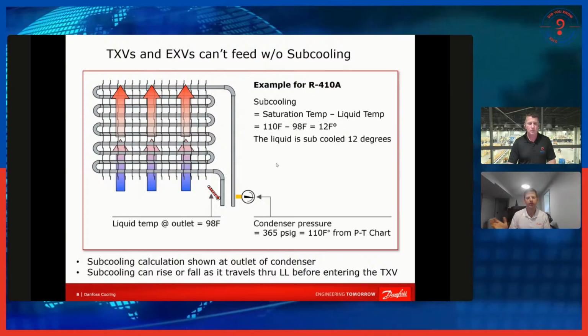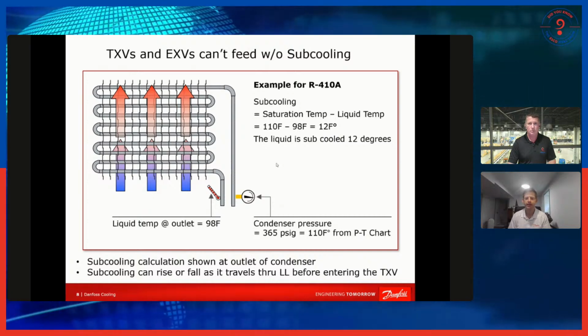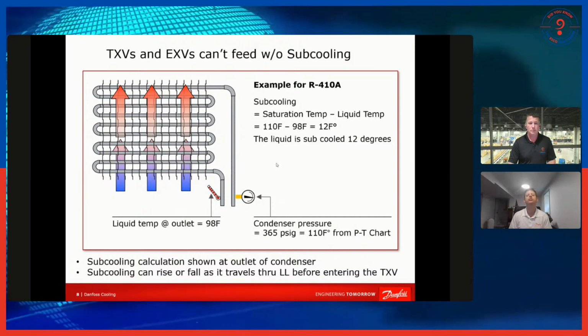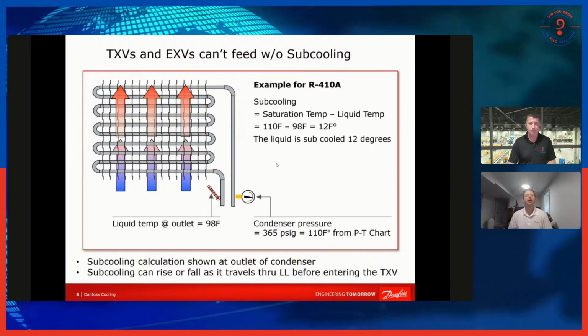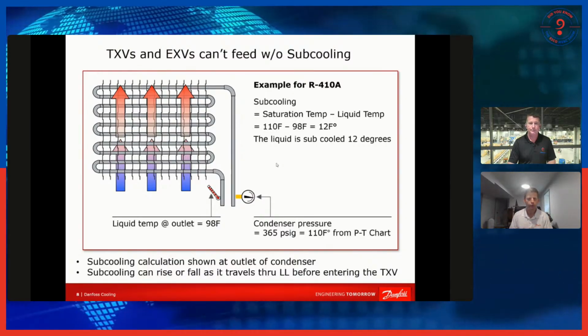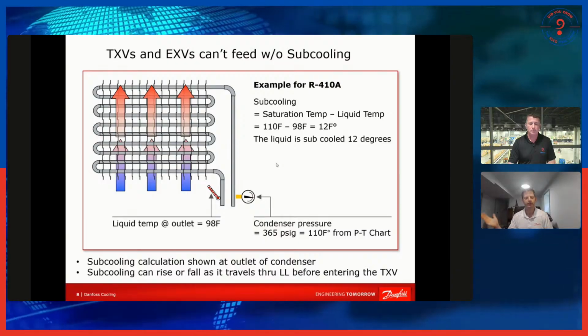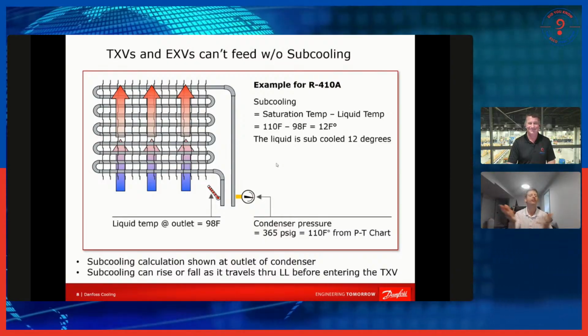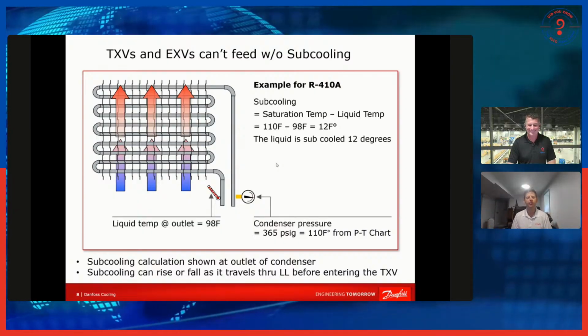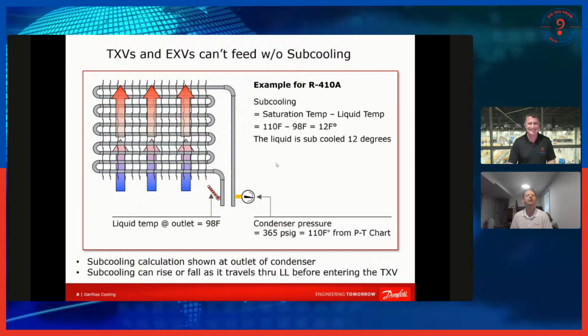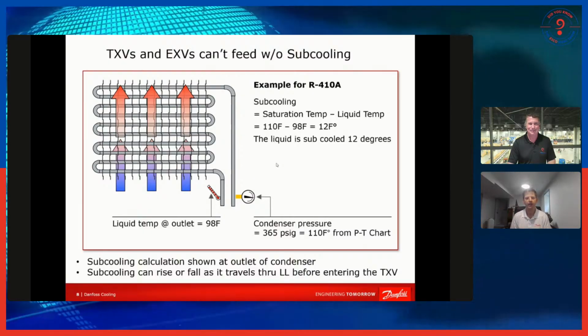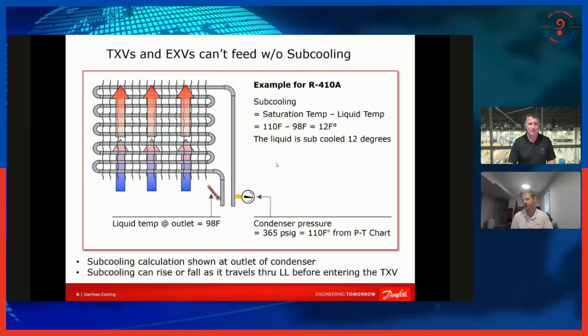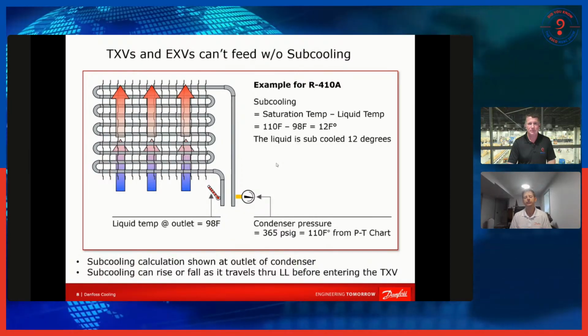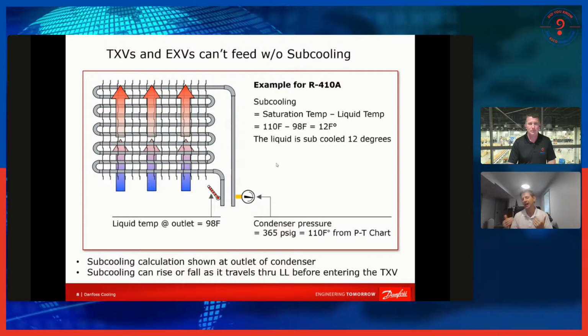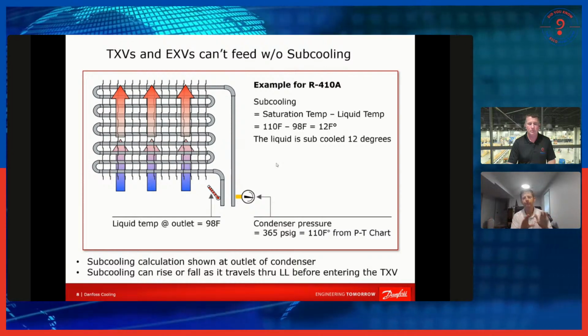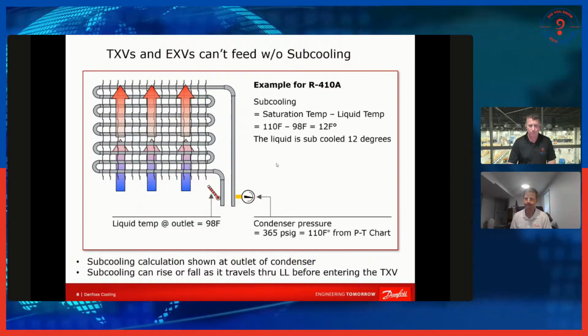If you have little to no subcooling, you should also have high superheat, and there's nothing that a TXV or EXV could do to fix that. You have to, whether it's clean your condenser, add more charge, find the kink in the liquid line, whatever it may be, replace your filter dryer. I probably could go on and say more things that it could be, but superheat and subcooling, they're basics, but they're important for a reason, because they can tell you a lot about what's going on in a system, and they can also give you a lot of good ideas on how to go search for what the problem might be.